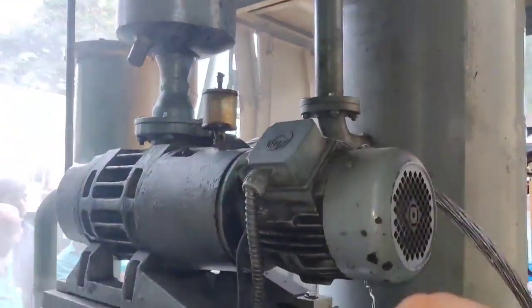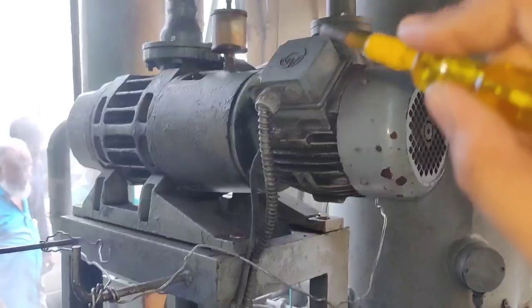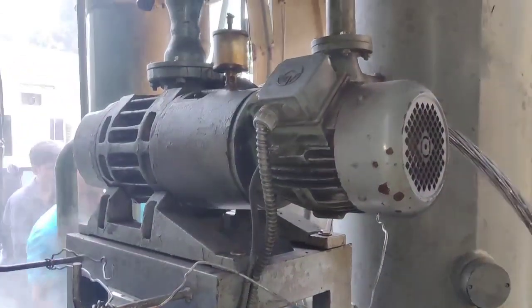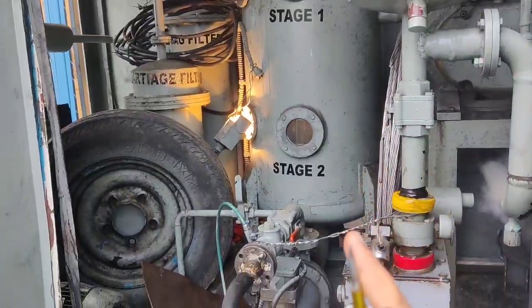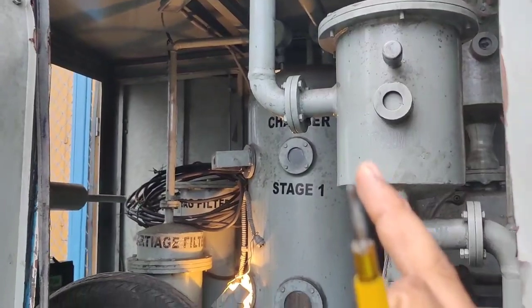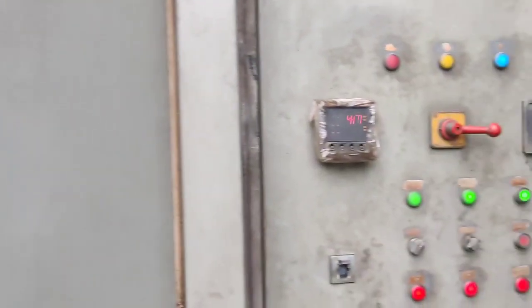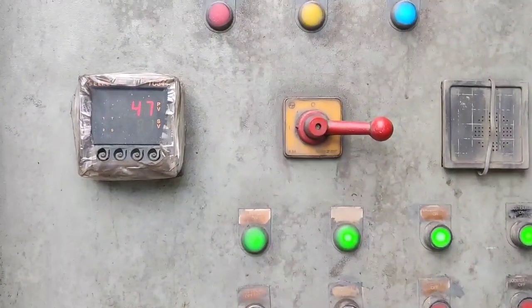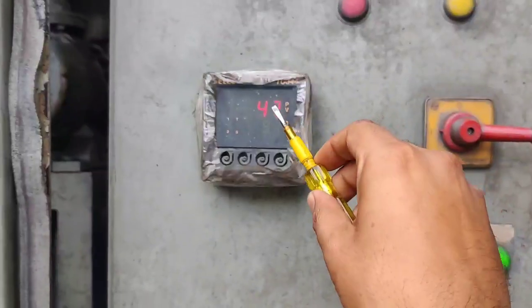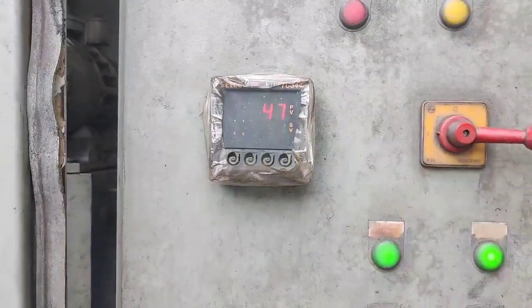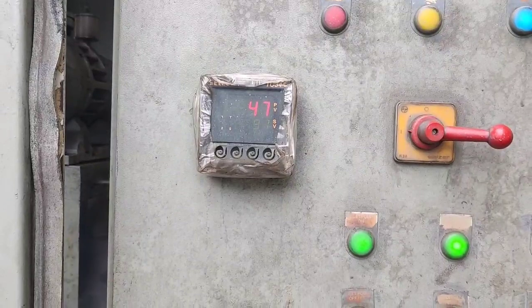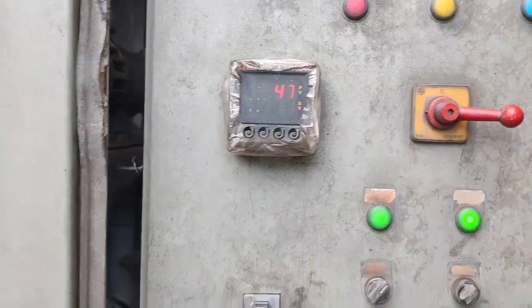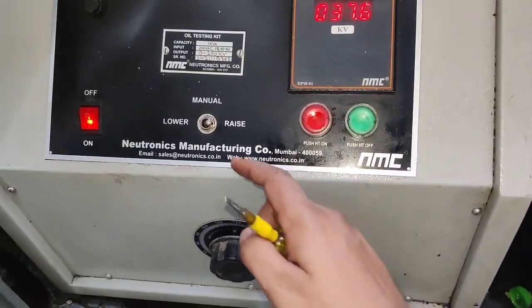If the BDV value is below 30 kilovolt, then you need to filter your transformer oil. A good transformer oil BDV value should be more than 35 to 40 kilovolt. If your transformer BDV value is less than 30, then you need to filter your transformer oil, and after filtration, you can use it. So I hope the concept is clear: how to check transformer oil BDV value and how much BDV value should come.